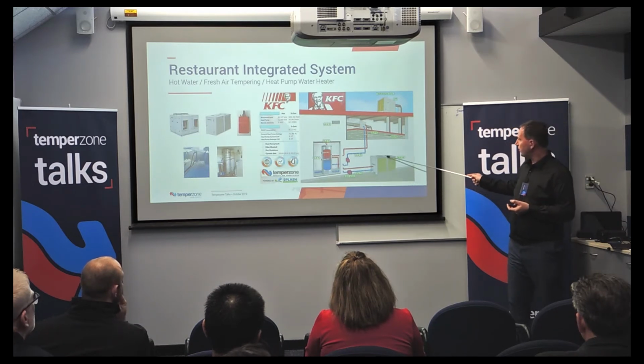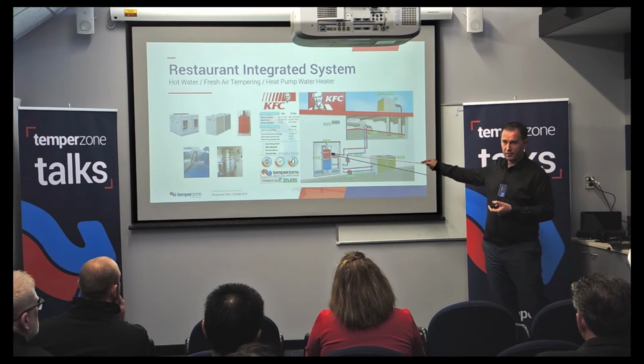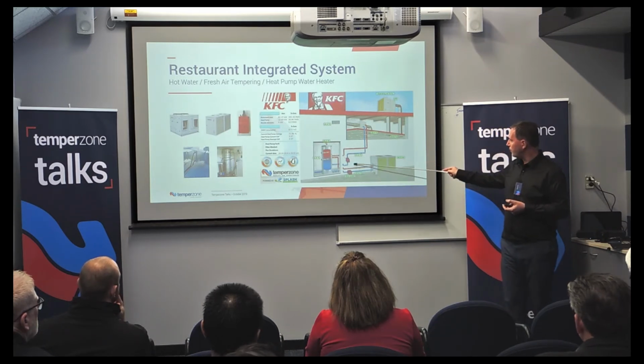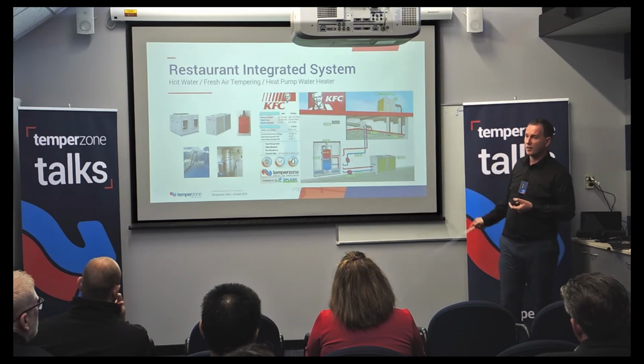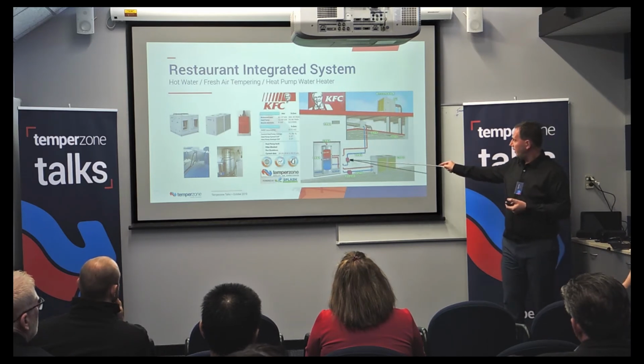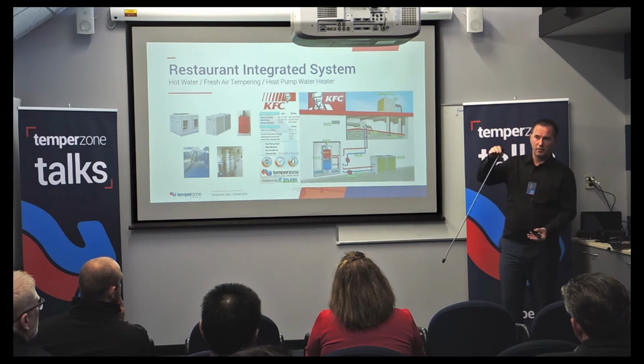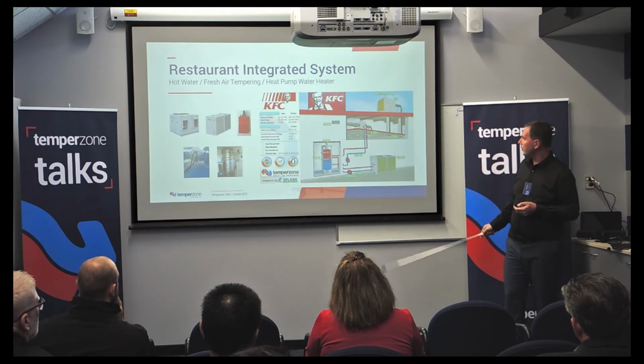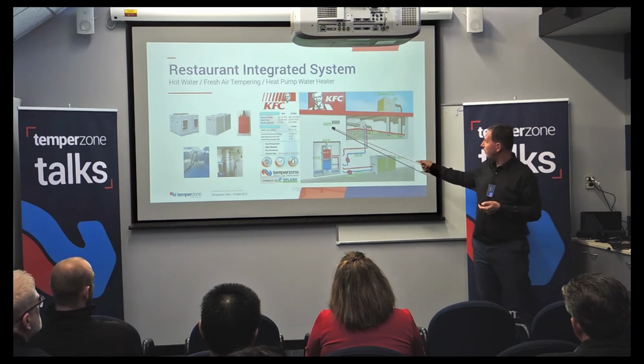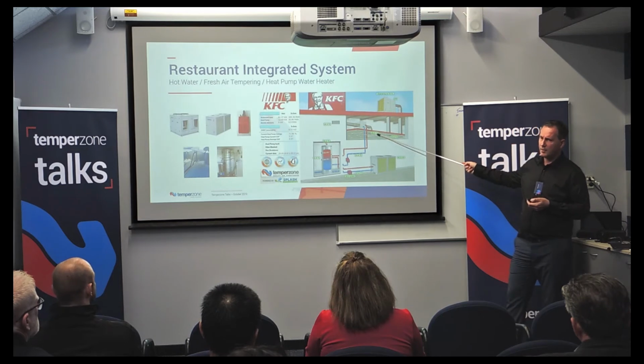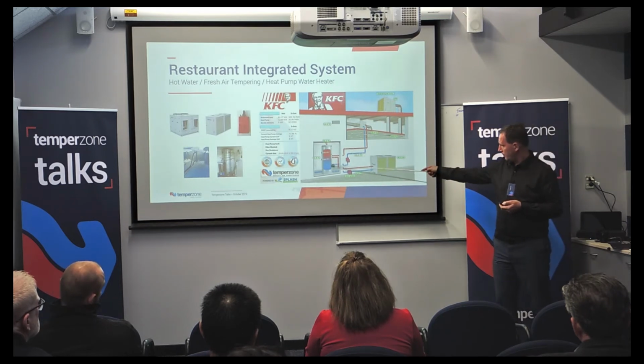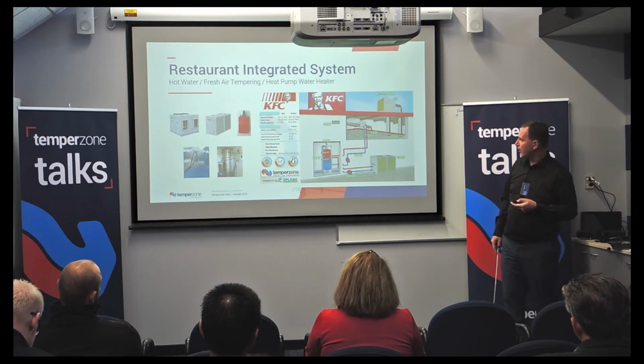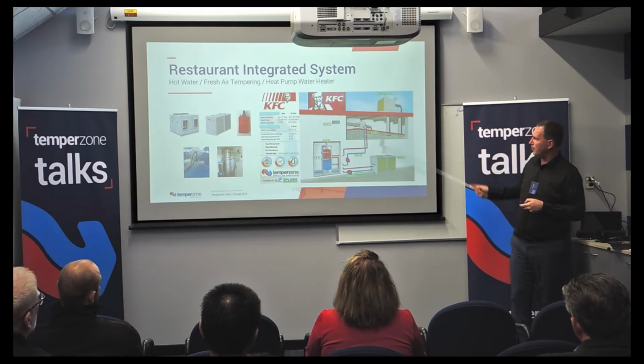So we've got a variable speed pump in the unit that maintains a fixed level water temperature of the heat pump, and then we've got a variable speed pump in the fresh air tempering side to maintain a cold return to keep the tank permanently stratified, which is where we get the efficiency from.